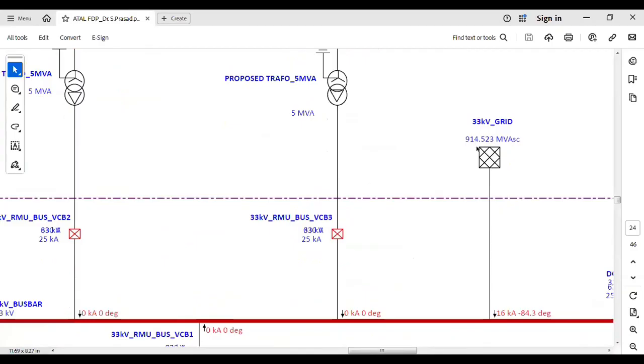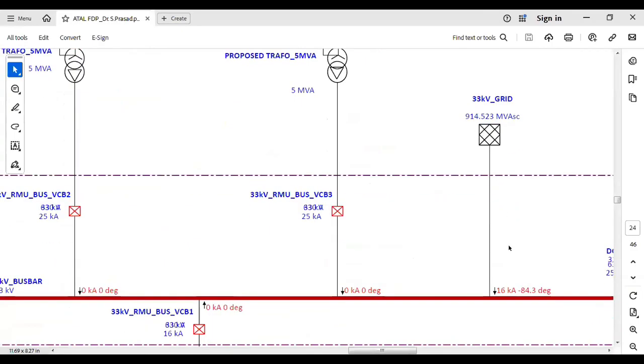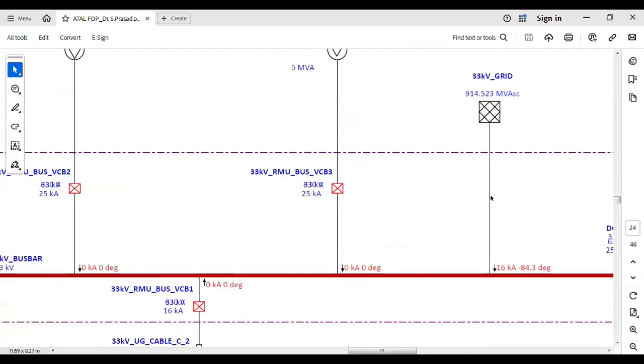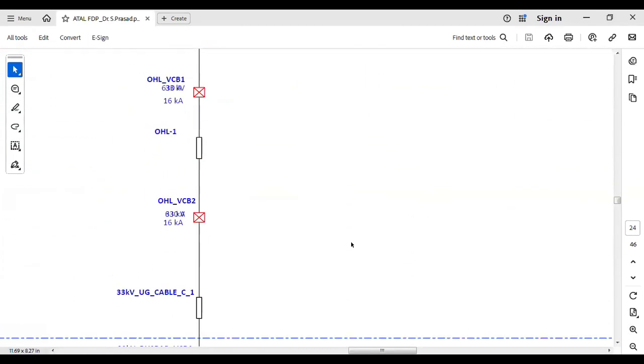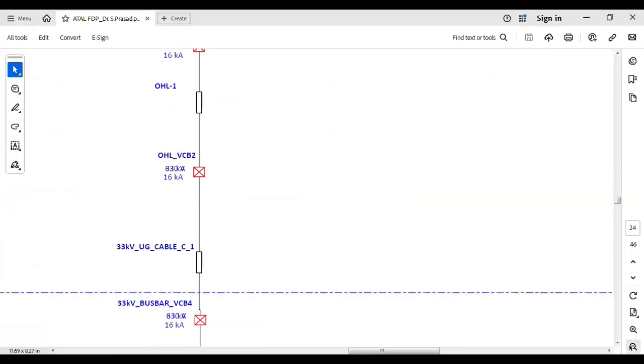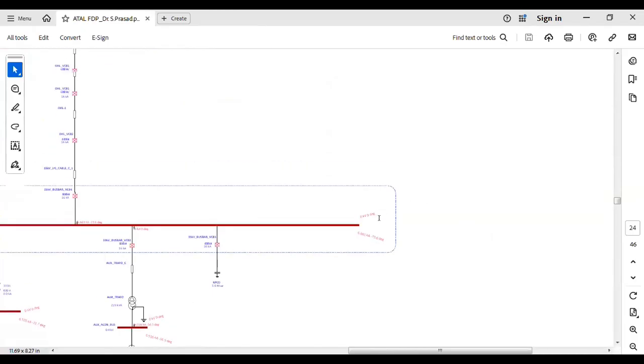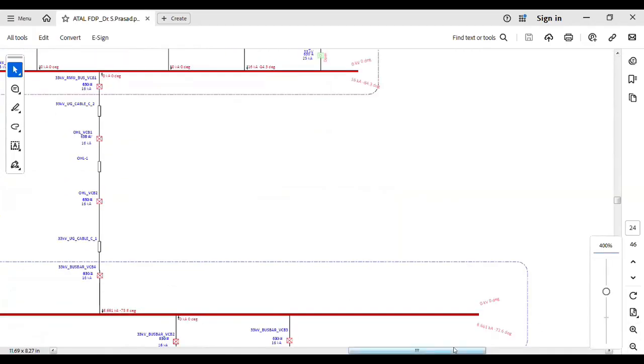Here you can see the 33 kV grid. The MVA rating is 914.523 MVA short circuit. Whenever a three-phase short circuit happens, the short circuit current contributed by the grid is 16 kiloampere. So 16 kiloampere of fault current will be injected at the point of interconnection due to the grid. Okay, so that will be specified. And you can see here at different buses what the short circuit current is, including the bus where the PV plant is injected at the 33 kV bus. You see what the fault current is. This is an important task we have to follow.